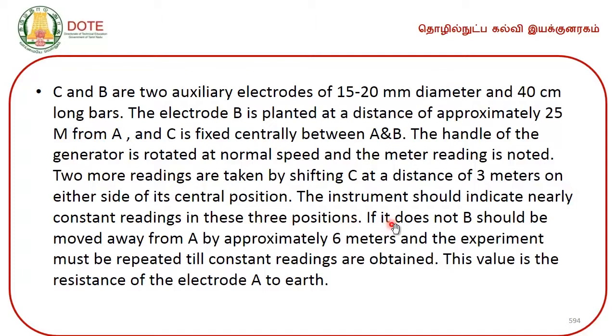If it does not, then B should be moved away from A by approximately 6 meters and the experiment must be repeated till constant readings are obtained. This value is the resistance of the electrode A to earth.